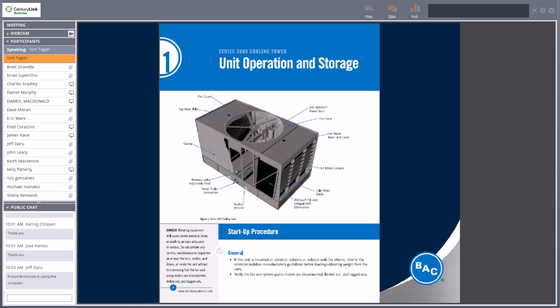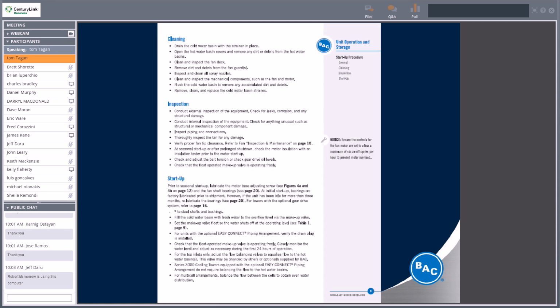So again, the reason I like these pages is it shows, which you probably can't see, the fan guard, top water inlet, casing, makeup water valve, adjustable float. It just gives you a breakdown of the unit so that if you are calling the factory or your rep to replace some parts, everyone's using the same language so that we don't end up shipping you the wrong part and you don't schedule a shutdown on Saturday morning only to find out we got the wrong part because we weren't speaking the same language.